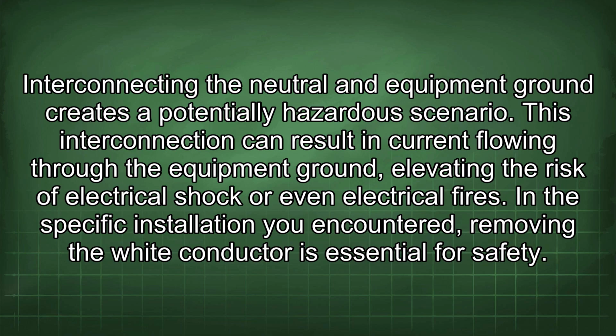Interconnecting the neutral and equipment ground creates a potentially hazardous scenario. This interconnection can result in current flowing through the equipment ground, elevating the risk of electrical shock or even electrical fires. In the specific installation you encountered, removing the white conductor is essential for safety.